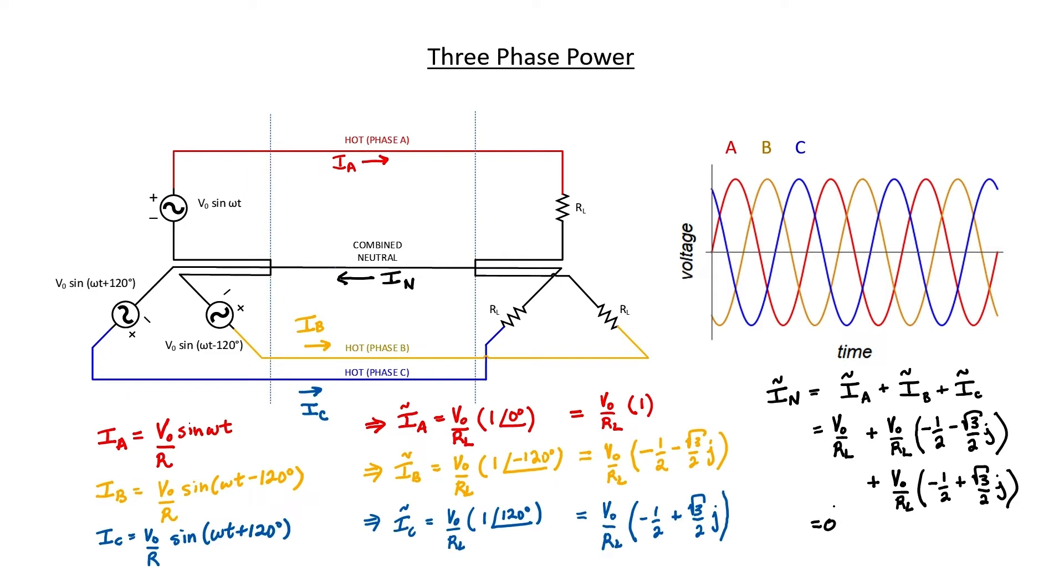That's the advantage of three-phase power distribution. We don't need a neutral at all. I could just simply get rid of the neutral wire. Now of course, all of this depends on everything being balanced. The amplitudes have to be the same in each of the three phases. The loads, the resistive loads, have to be the same as well. But assuming that you can maintain balance in your power network, then you don't need a neutral return wire. That saves a lot of copper.